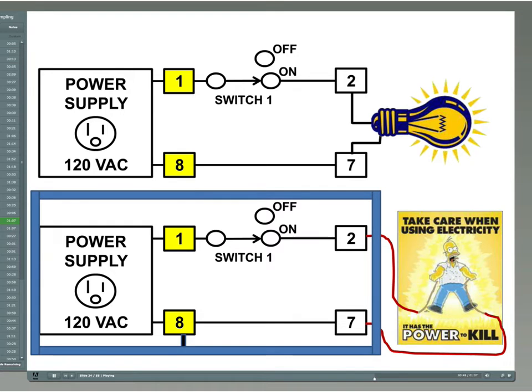Standing in shoes with wet boots on wet ground while touching the power supply terminals could also kill you. Wear PPE when possible. Ground one lead of the voltmeter with a clip lead and probe with one hand. If only one limb comes in contact with voltage, the chances of injury are minimized to slim or none.